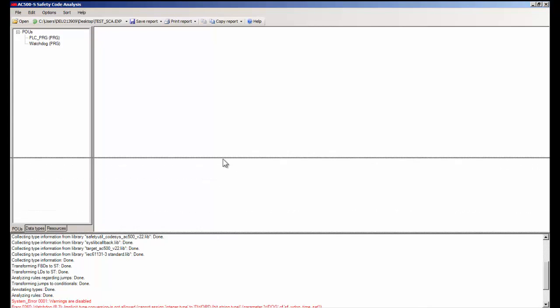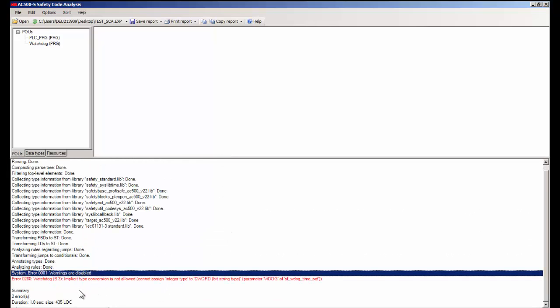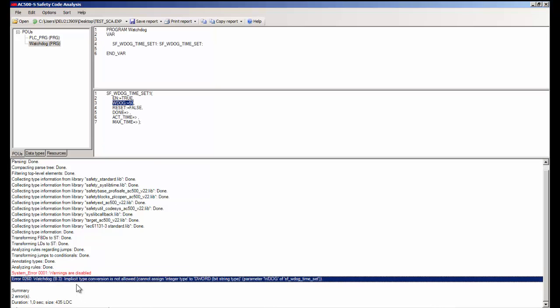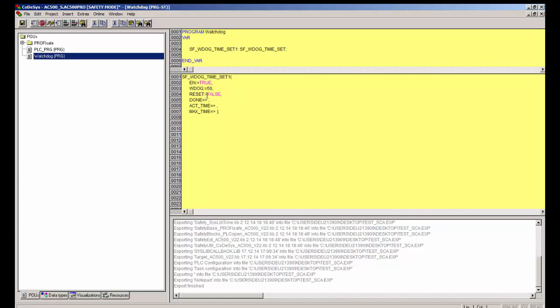Automatically the exported safety codes will be analyzed and a text report will be displayed in the message window. Errors will be notified with red color text giving out details like error number, error location, and error description. The user could now make necessary further changes in the IEC editor and perform subsequent text file export function as done before, as many times as needed.